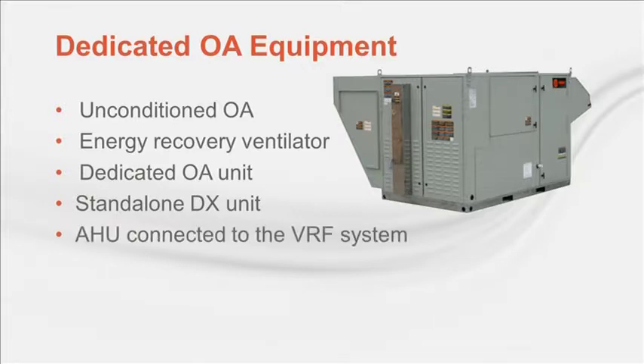But other systems use an air handler where the DX coil is connected to a VRF system. This can allow for simultaneous cooling and heat recovery during colder months, if the system also serves the interior zones that still require cooling, while the outdoor air must be heated. However, remember that in the summer, both the outdoor air unit and indoor units will be in cooling, so you're limited on the circuit size. And at least today, there's often a low limit on how cold of air can be heated, possibly requiring the addition of preheat.